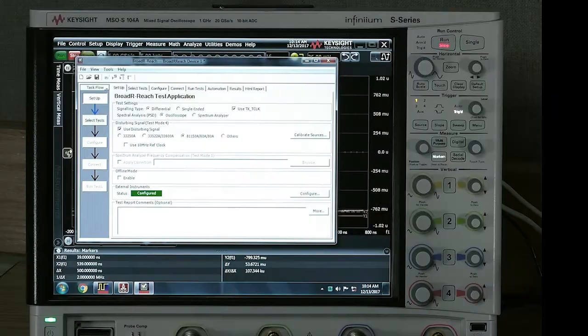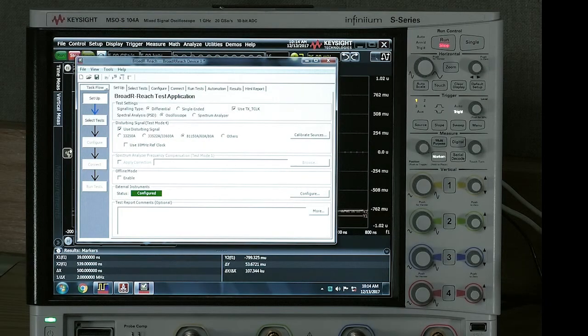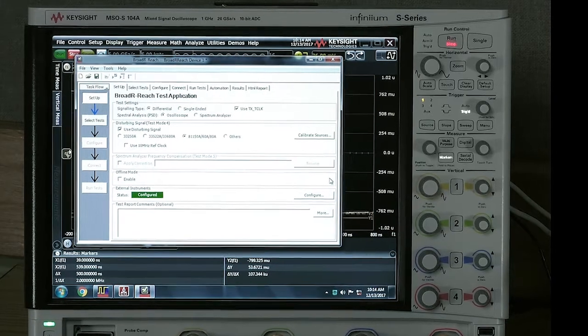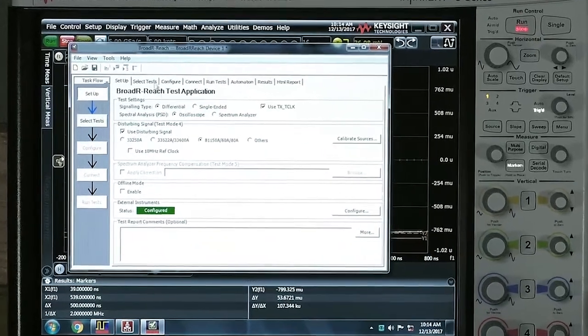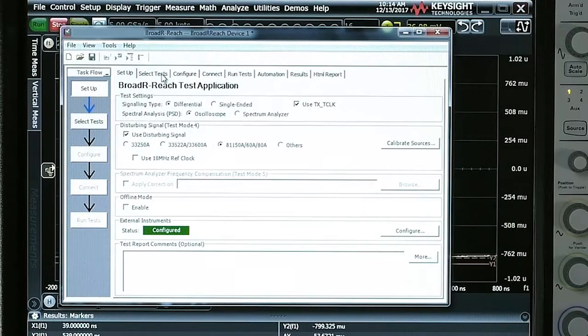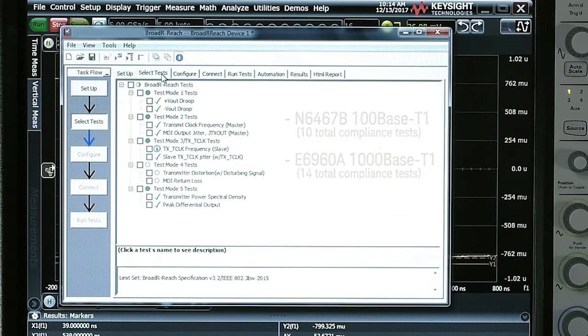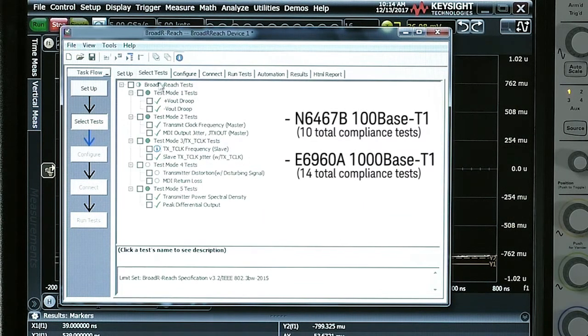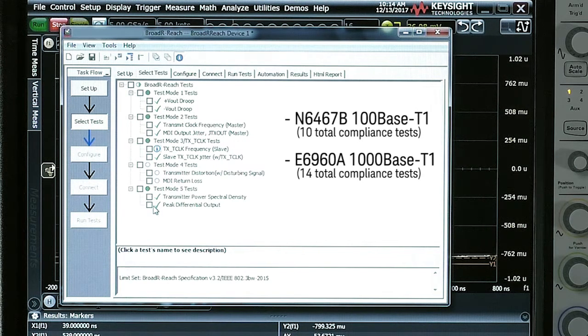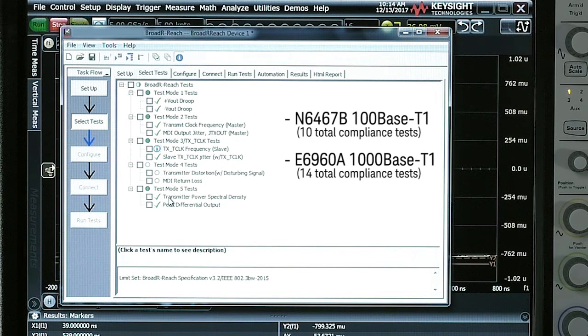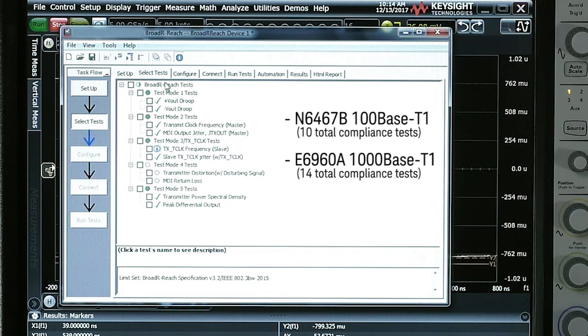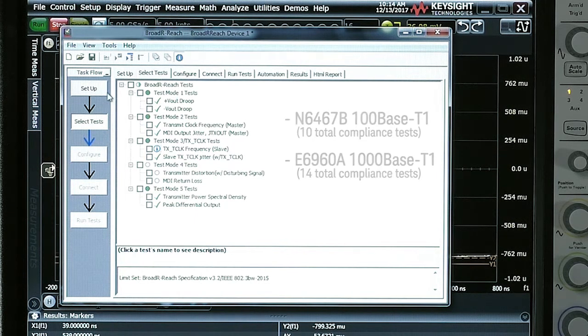First things first, we're going to set up the compliance application to see if the signal will pass the transmission specification for IEEE. What we're looking at here is a 100Base-T1 compliance application. You can see there's 10 total tests, these are defined by IEEE. Keysight also has a 1000Base-T1 application and there are 14 total tests, so there's a couple more tests there.